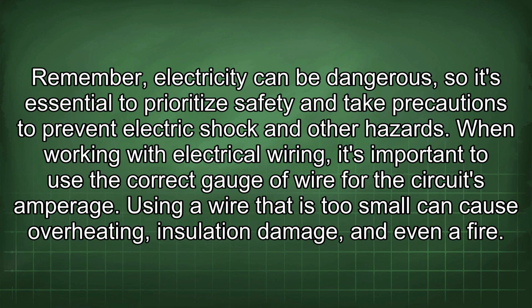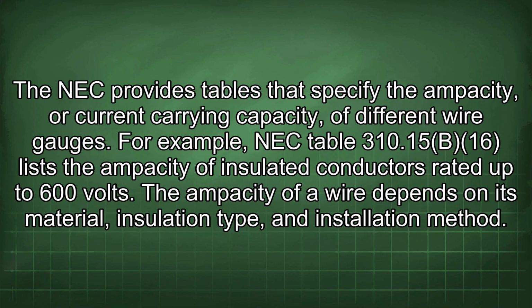Using a wire that is too small can cause overheating, insulation damage, and even a fire. The NEC provides tables that specify the ampacity, or current carrying capacity, of different wire gauges. For example, NEC Table 310.15(B)(16) lists the ampacity of insulated conductors rated up to 600 volts. The ampacity of a wire depends on its material, insulation type, and installation method.